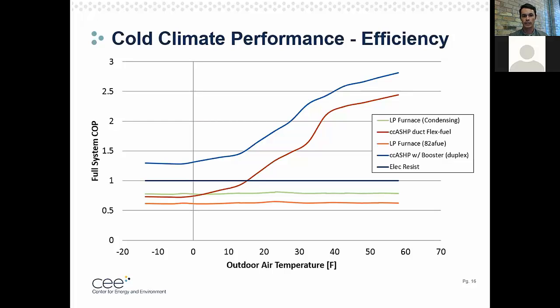You'll notice the horizontal lines around the bottom are your traditional HVAC systems. The dark line right along 1 is an electric resistance system, so that's 100% efficiency. The 2 lines below that are your condensing and non-condensing furnaces. For those systems, it doesn't matter what the outdoor air temperature is, that's the efficiency they operate at, and you'll see those are below 1. Our y-axis is the coefficient of performance: 1 is electric resistance, 100% efficient, with all the heat going into heating that space, and below 1 you have your condensing and non-condensing furnace. The x-axis is temperature.